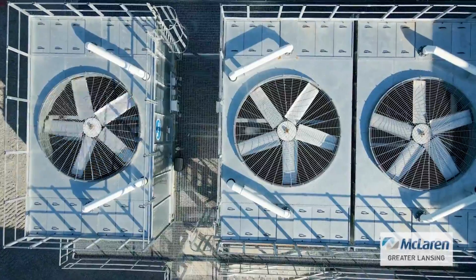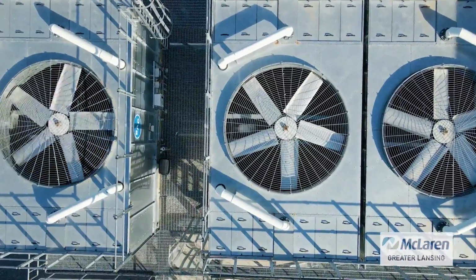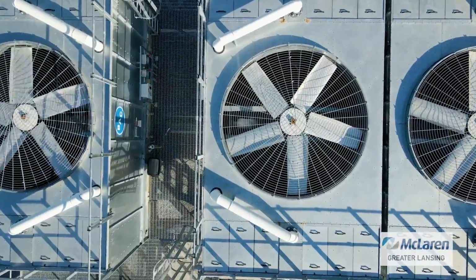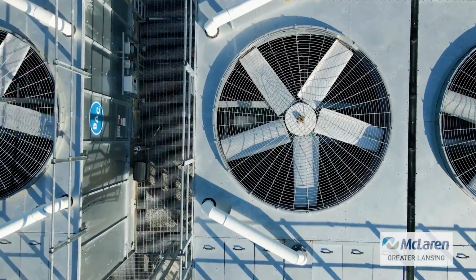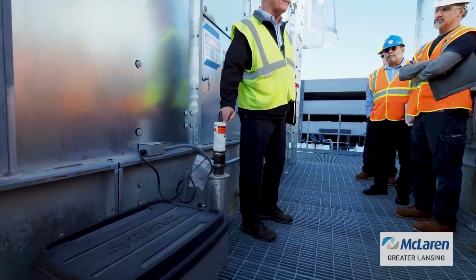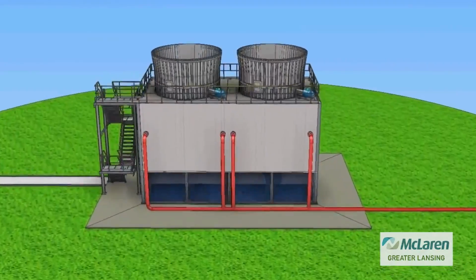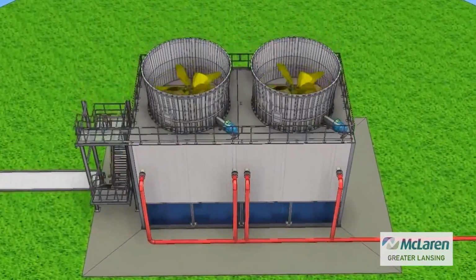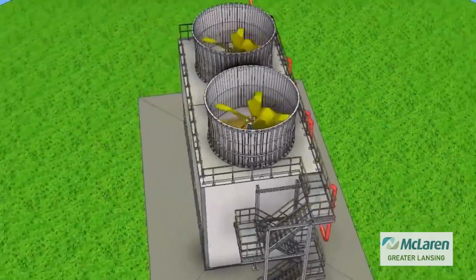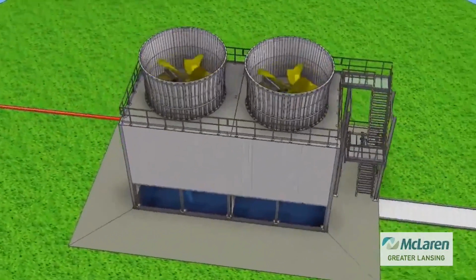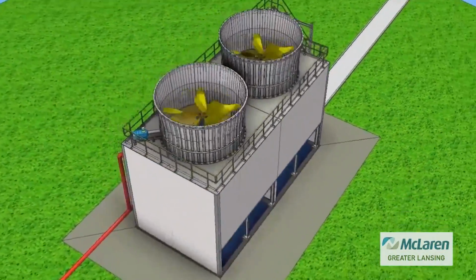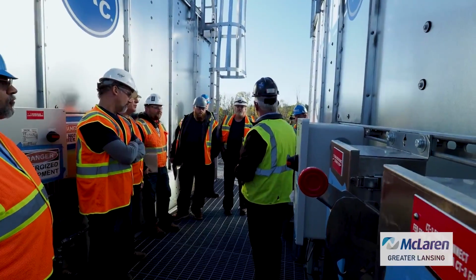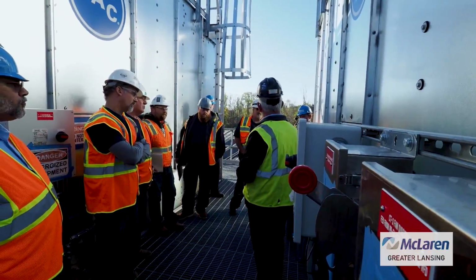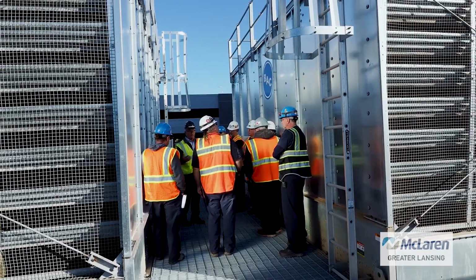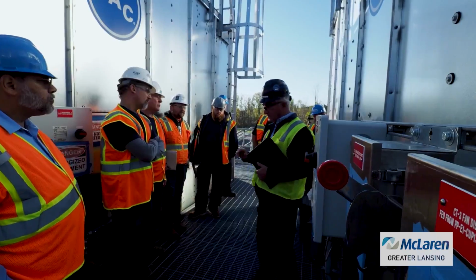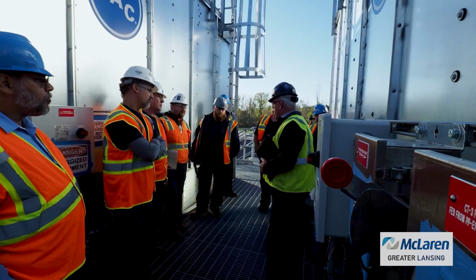The little flash, the LED here is solid red, all good. There are little error codes on the side of this. And this has a call for makeup water. A solenoid valve inside introduces the makeup water into the suction header. So again, if we're running 2250 GPM out of the tower, if you're going to be putting your hands in the water, keep in mind it's chemically treated. I would suggest wearing rubber gloves. I would suggest washing your hands shortly after getting out of the tower.